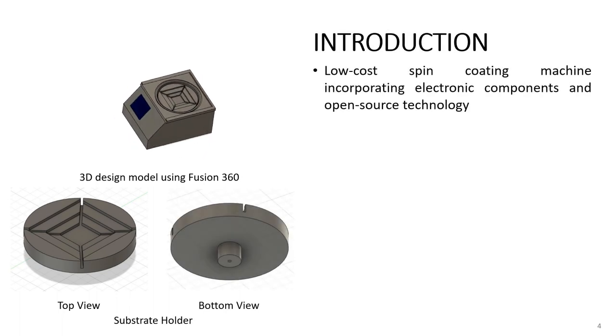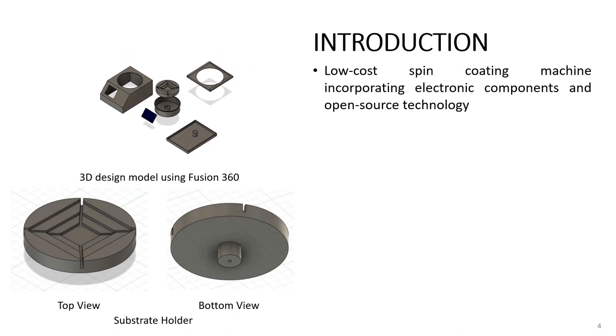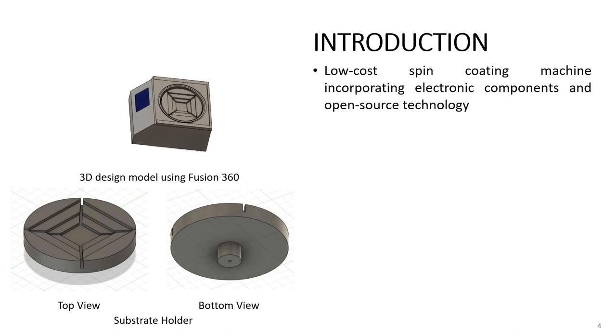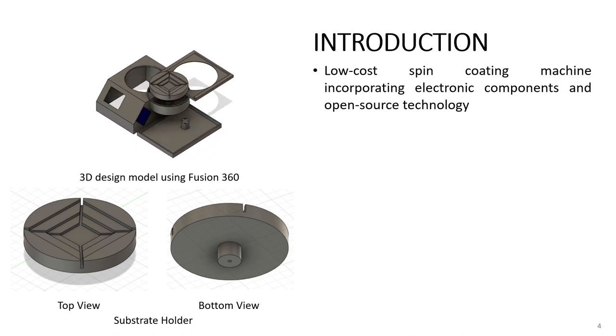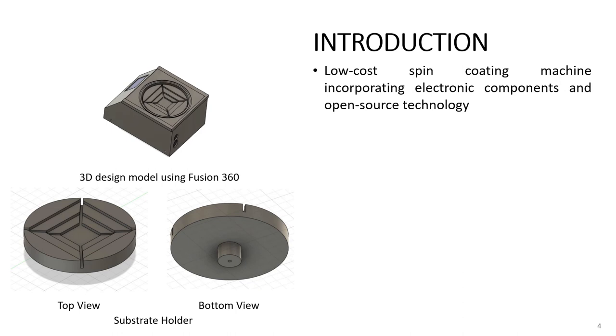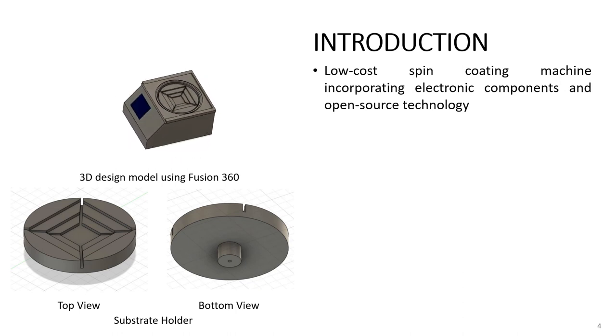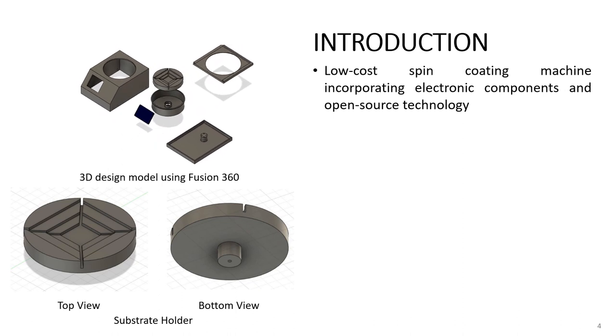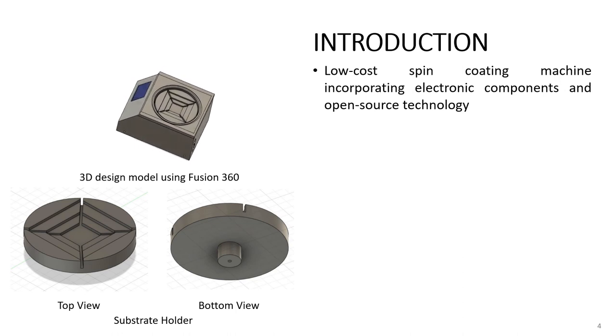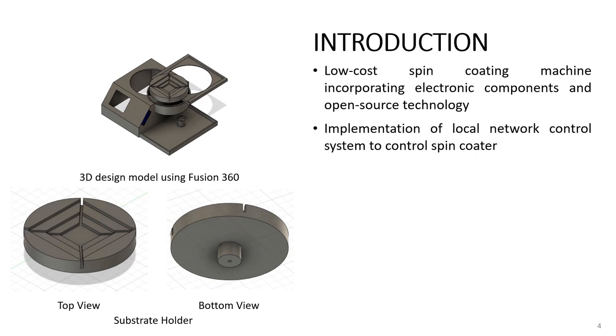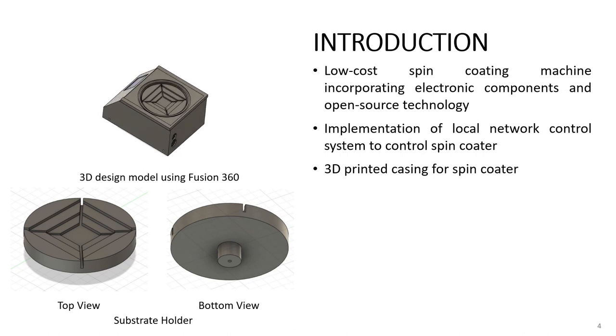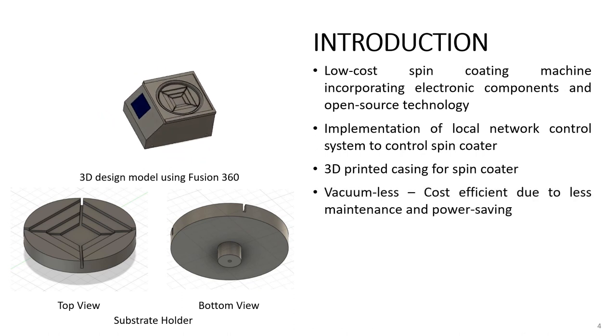This project is about constructing a programmable, low-cost spin coating machine incorporating inexpensive electronic components and open-source technology. Most conventional spin coaters are expensive to purchase and do not have a database system to store data for future reference. The system was designed using a microcontroller as the main system and a brush motor to spin the substrate. It is capable of spinning around 300 to 5,000 RPM, controlled manually and automatically. Using a local area network, the system can store data by uploading it to a notepad for future reference, and uses an LCD screen to display job settings during operation.